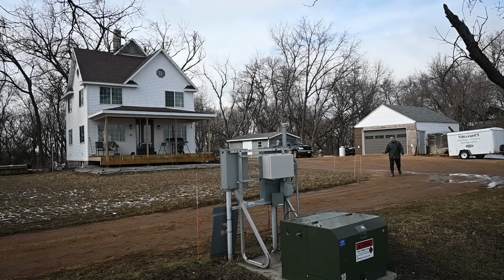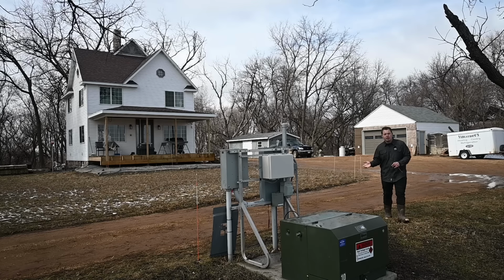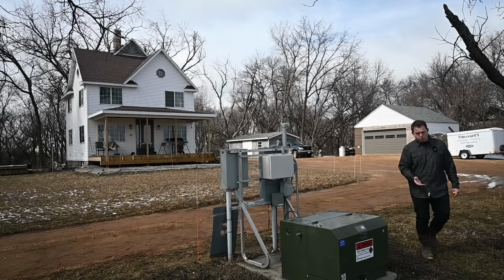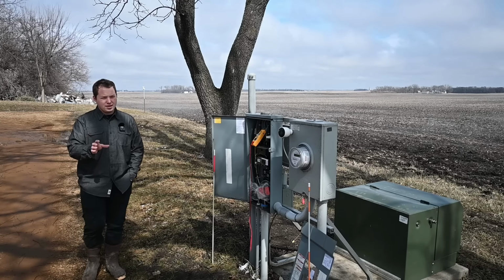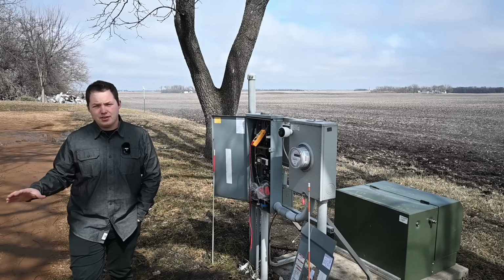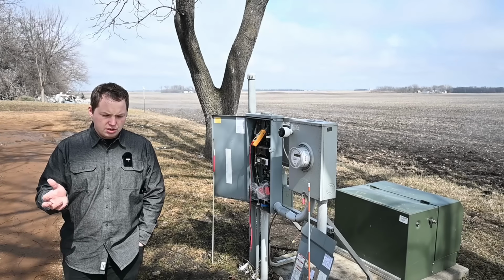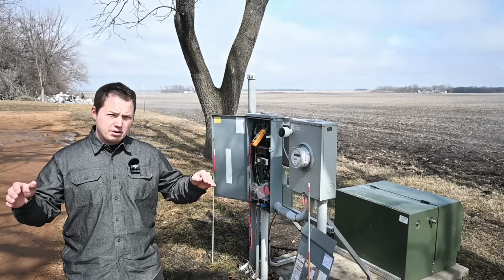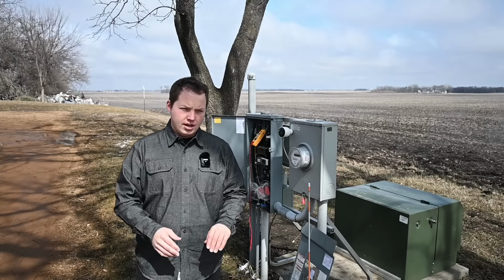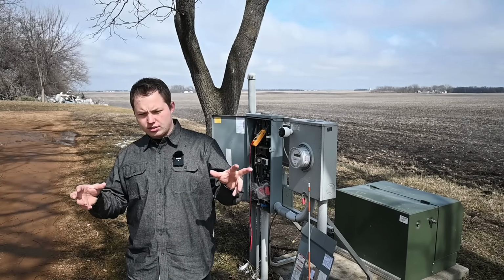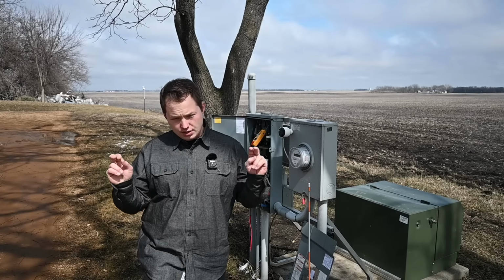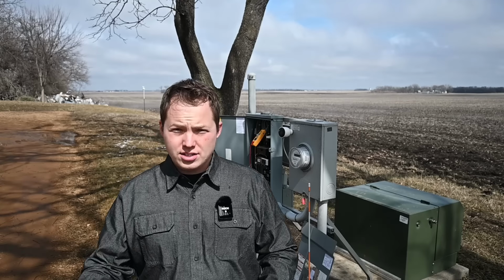Because even with all of the circuits turned off, the grounding system stays fully connected. When you turn off a breaker, it only disconnects the hot wire and not the ground or the neutral. So this brings up a whole new thing that I do not understand, and it relates to whether or not electricity wants to go to ground. Now, when we talk about electricity, I always thought it wanted to find the shortest path to ground. It's actually not the shortest path. It's all paths back to the source, not necessarily to ground.